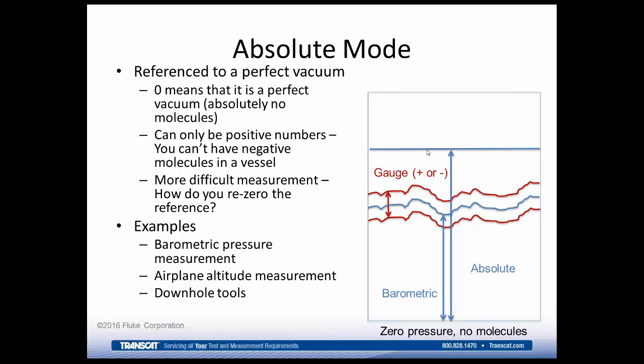With absolute mode, it gets much more difficult because the only place where it should specifically read 0 is at a perfect vacuum, which, as we said, is pretty much impossible. So to zero an absolute device, you really need a device that's more accurate than it that you zero it against. So if you turn your device on, you open it up to atmosphere, it's reading something like 14.7 psi absolute. You then have a very accurate barometer that tells you that no, actually the barometric pressure in the room is 14.685. And so you know that, okay, we can correct it: instead of 14.7, it should be reading 14.685.